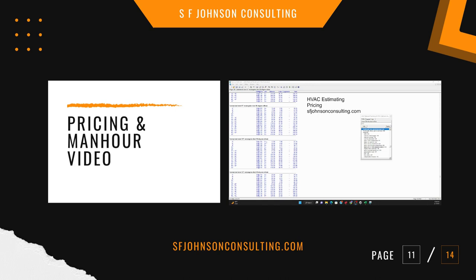And here is the size, and here, if you can see that in this presentation, that's the material cost, but the number, and you'll have the PDF, so you'll be able to see it very clear, but the number after the @ sign is the man hour total, meaning that's what portion of an hour it takes to install one unit. And with ductwork, a unit is 1 linear foot. And so if you know how many linear feet, then you can determine how long it's going to take you to do your complete job, because we have that same information for everything in construction: ductwork, grills, equipment, insulation, everything.